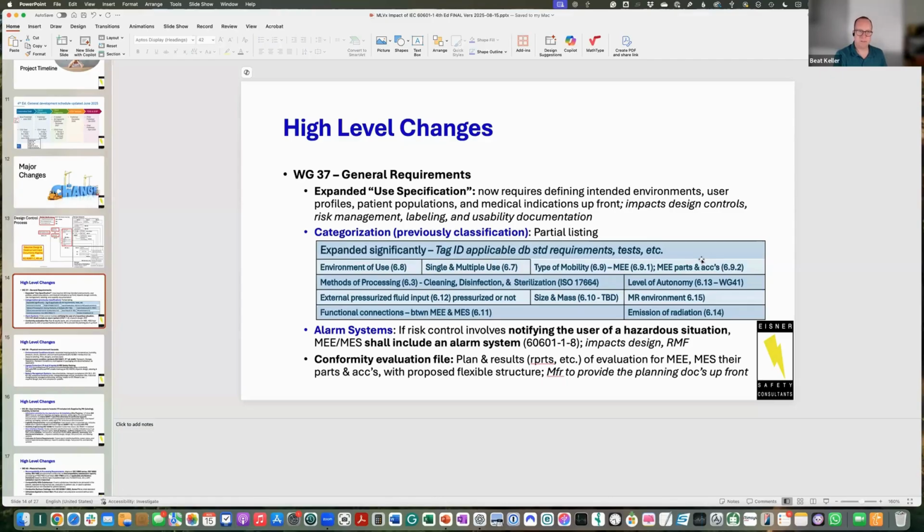So once all the devices on the European market need to be compliant with the 4th edition, as this will once be seen as the state of the art by the authorities and the notified bodies. And this happened very similarly with the 3rd edition too. The same will be with the 2nd edition of the IEC 62304 software standard. Which will be out a little bit earlier, probably. That's the hope.